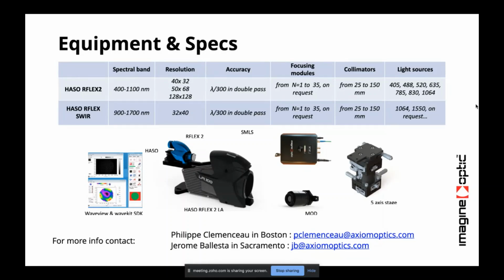Because if you allow the customer to change the magnification, you could interpret the data that is displayed completely wrongly. So it's a choice that we made. The only answer I can give is to extract the data file from the wavefront sensor software and do the magnification yourself using your preferred tool, Excel or Python or I don't know.